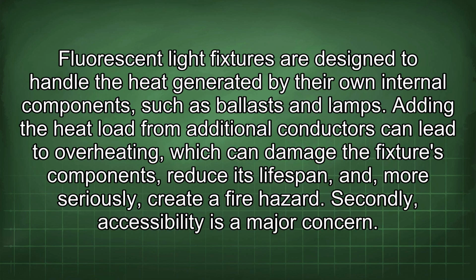Fluorescent light fixtures are designed to handle the heat generated by their own internal components, such as ballasts and lamps. Adding the heat load from additional conductors can lead to overheating, which can damage the fixture's components, reduce its lifespan, and, more seriously, create a fire hazard.